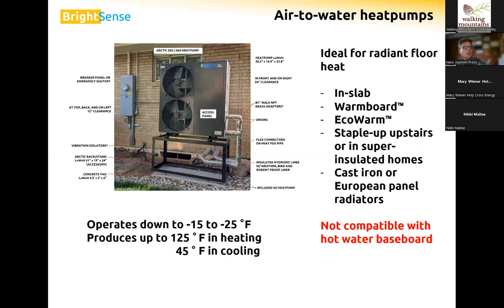So sometimes, when the heat exchanger itself, where the thermal energy is absorbed, drops below the dew point, some frost will build up. And the frost hampers the heat transfer. So when the heat pump detects that, to a certain extent, it will go into defrost mode and melt that layer, and that results in some meltwater that will then collect underneath. If it's significantly below freezing, it will refreeze and form an ice sculpture underneath.